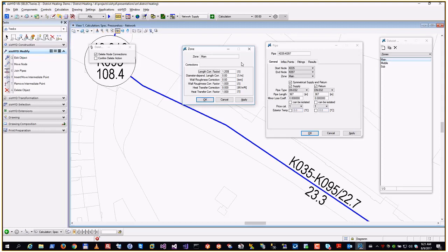When we are talking about pressure loss computation, there are different methods to correct pressure loss. One is this length correction factor. Another option is the wall roughness, because that influences the Reynolds factor. If you want to adjust your model results with reality, you can choose the length correction factor, or the alternative is the wall roughness. Whatever suits you best and makes the best synchronization of model results with reality.